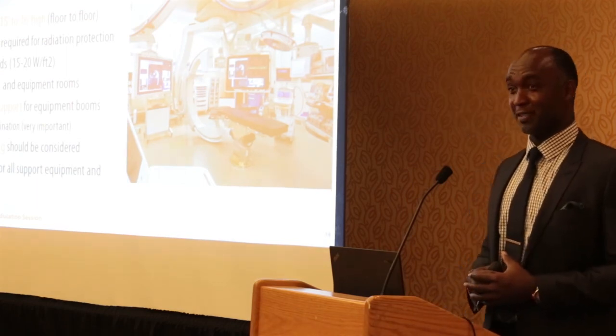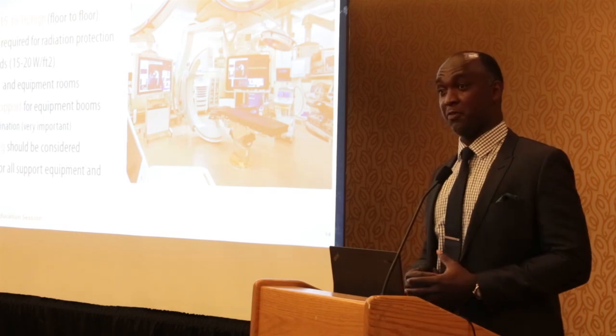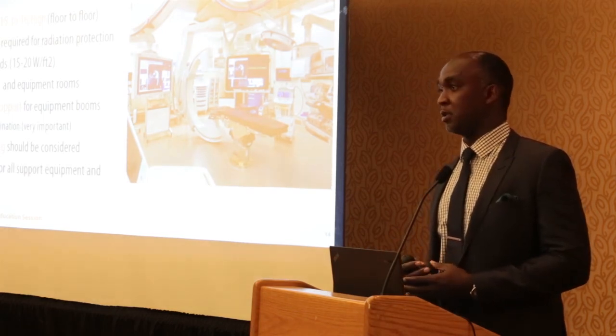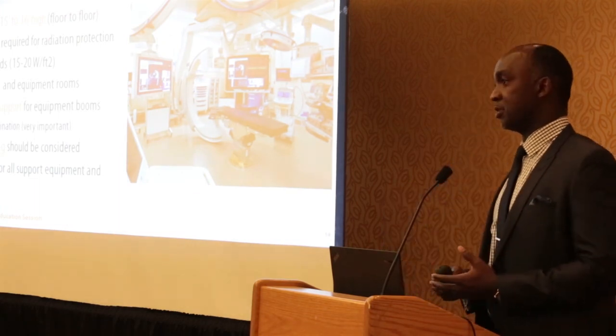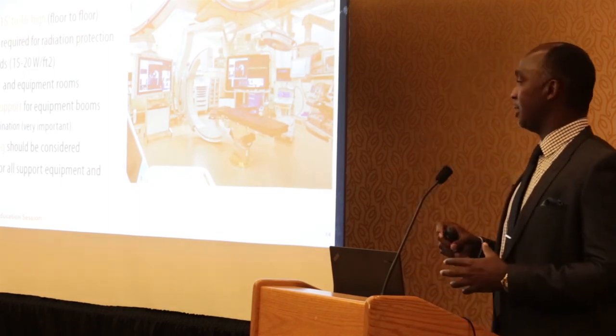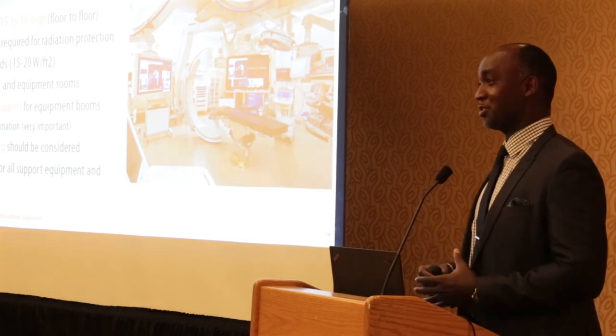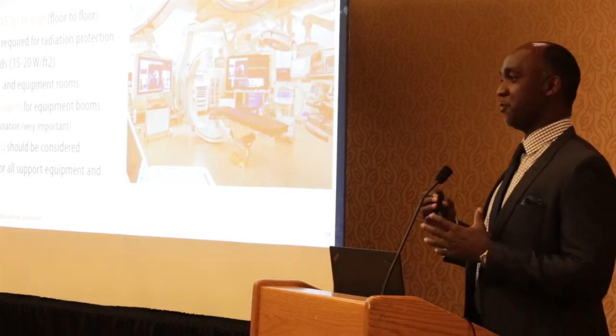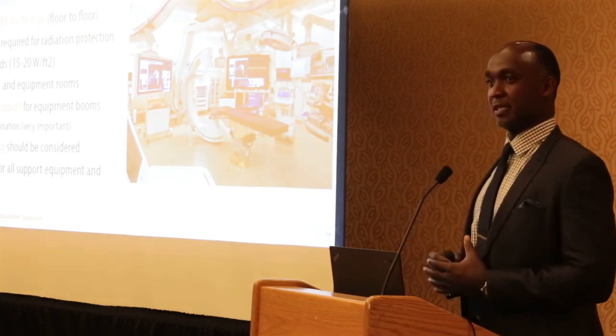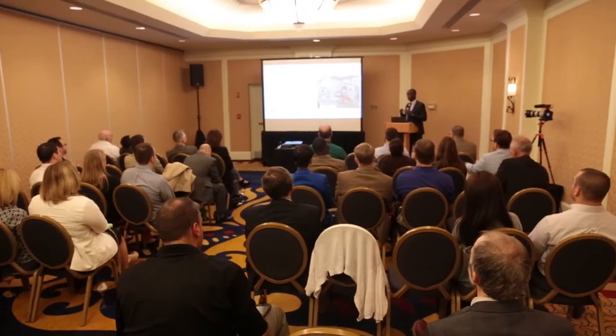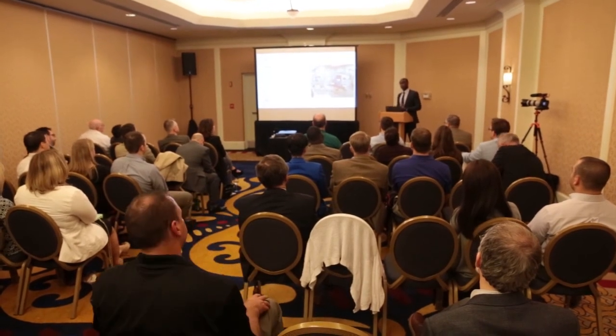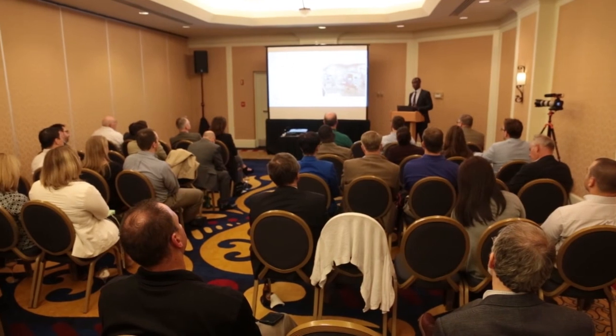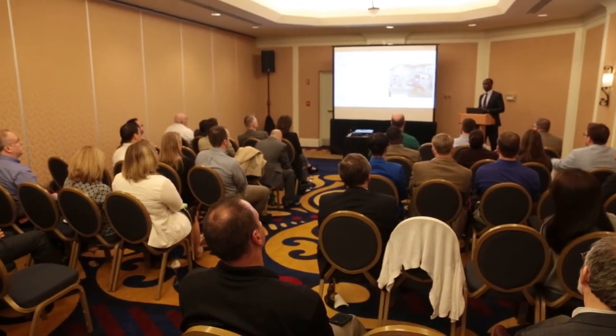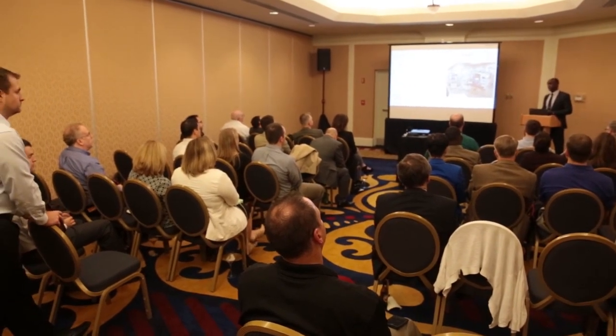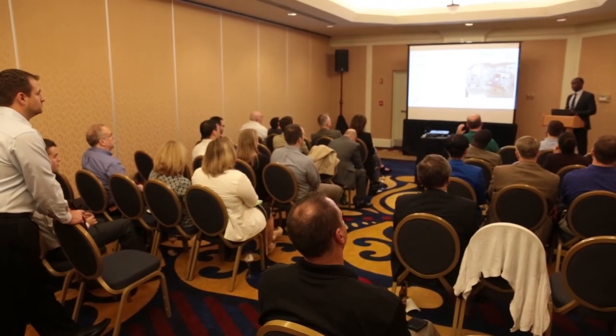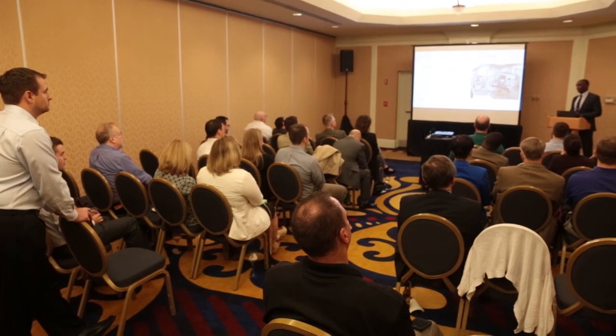Another thing we want to talk about is that you need a lot of ceiling height, 15 to 16 feet, the higher the better. There's a whole lot of equipment in the ceiling. There's ductwork, there's laminar diffusers, there's a C-arm for the imaging equipment. There's a whole lot of items that need to be coordinated and structurally supported within this space, and you have to maintain 10 feet of actual clearance to the ceiling so that you can navigate the space as best as possible. So if you're going to renovate a hospital to add a hybrid OR, and you have 12 to 13 foot floor to floor, I would recommend you do not try, because it's going to be extremely difficult. It's workable. You could try it, but it takes intense coordination and a whole lot of on-site coordination to get that done.